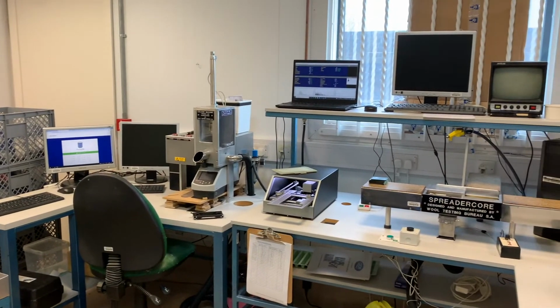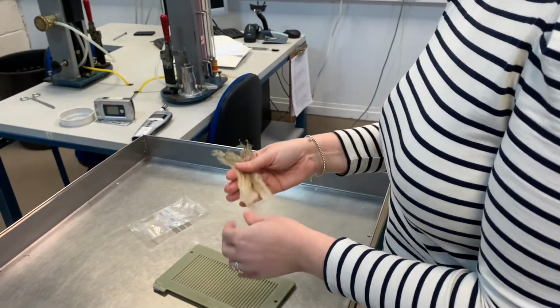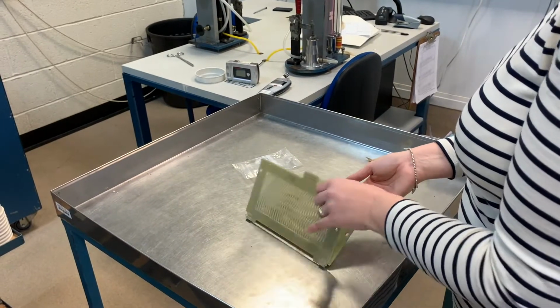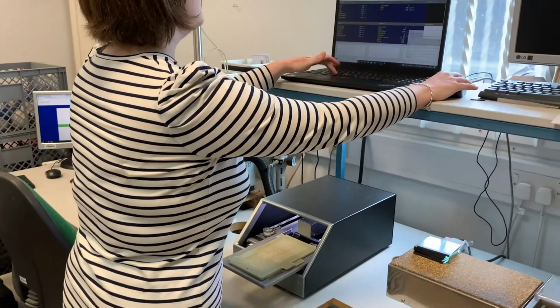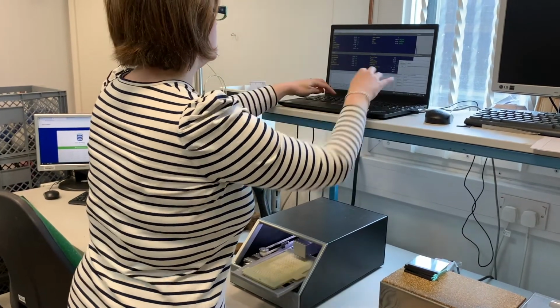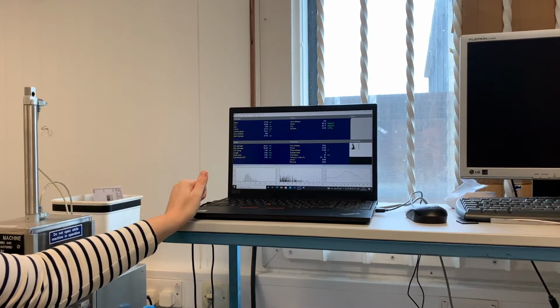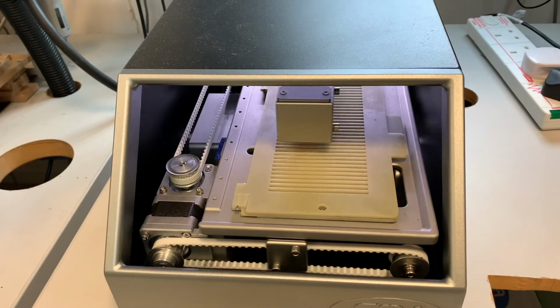To test a sample, the staple is laid on the testing grid, the grid is closed and placed onto the OFDA 2000. The test is initiated and the OFTA begins its work. The microscope tracks the length of the staple, measuring the fibre diameter as it moves, compiling a micron profile and histogram for that staple. The test is complete within 20 seconds.